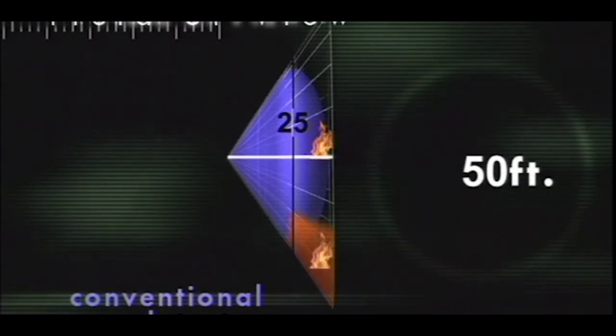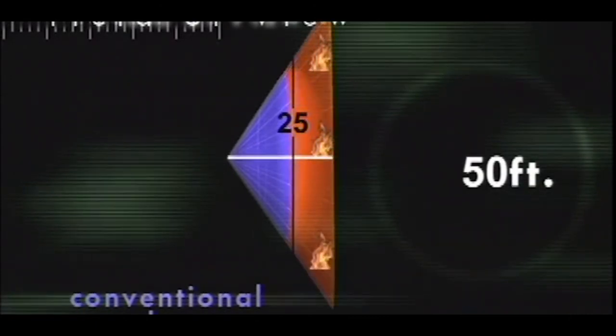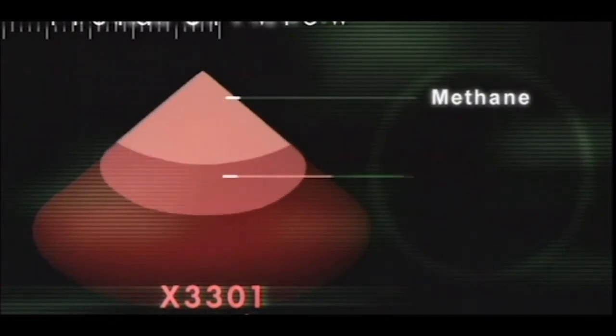As a result, any fires that occur outside this view will not be detected. Testing has shown that Protector has an on-axis range of up to 210 feet, with off-axis sensitivities up to 100%—a huge increase in the overall area of coverage. What's important to remember is that this increase is consistent across all types of fire.